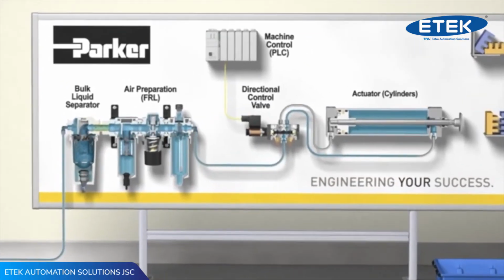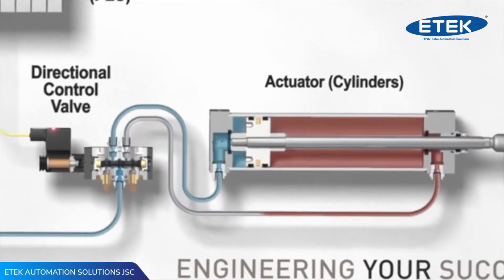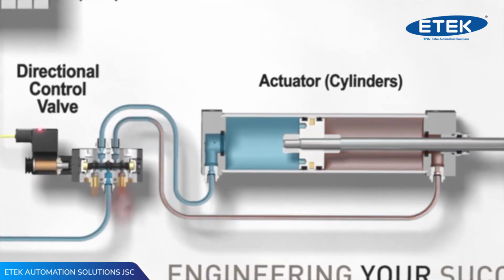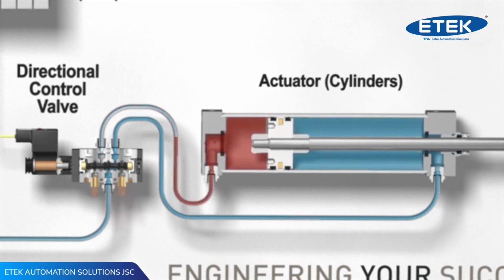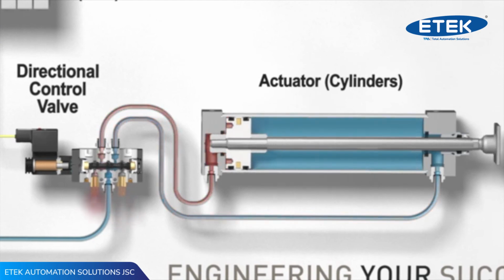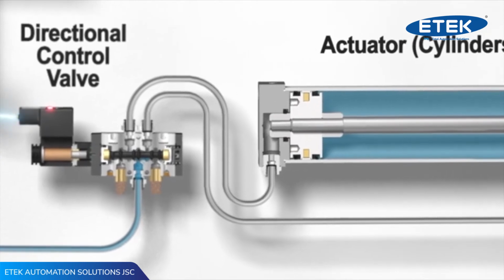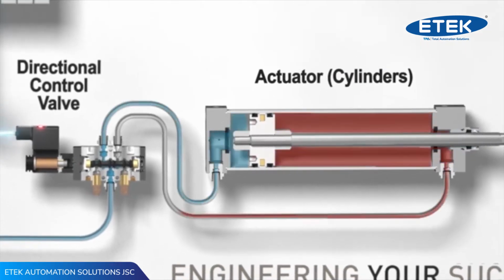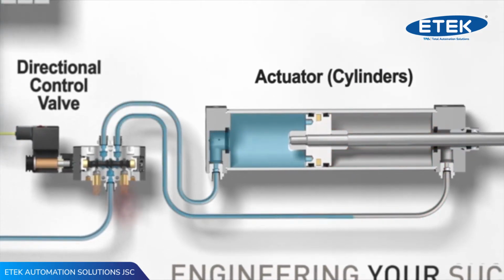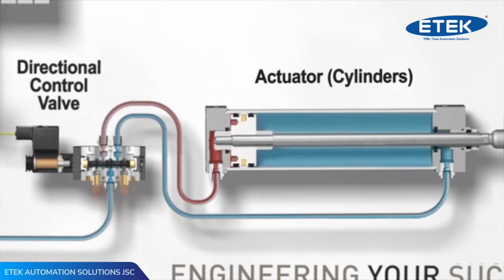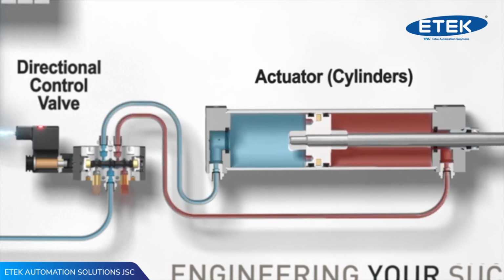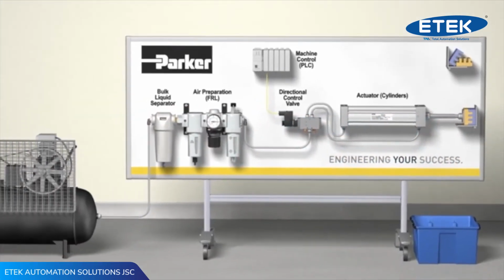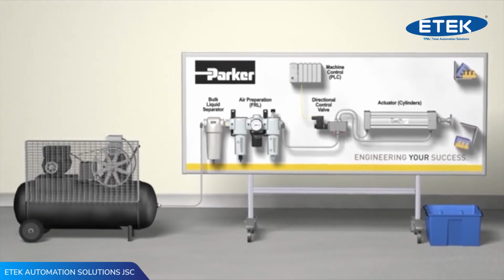This system can repeat this process as often as the PLC tells it to move things from point A to point B in one example. In this example, the PLC is telling the actuator to move this product by sending a signal to the directional control valve, which is using the clean, dry compressed energy to power the actuator. Pneumatics are also commonly used to press 2 components together in an assembly process to help form a finished good. Through the combination of Parker's air preparation, valve, and actuator products, there's a wide range of applications that can be solved.